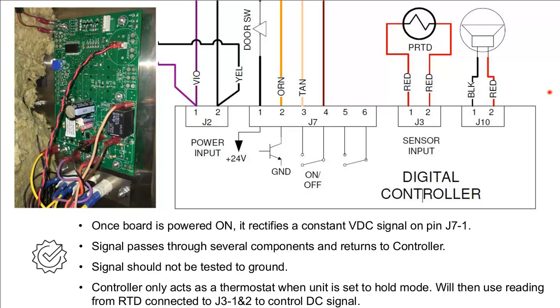I'll draw your attention to the fact that the controller does have an RTD. In cook mode, the controller outputs a constant DC signal. It does not modulate the signal based on the input of that RTD. The only time it will modulate that signal is when the unit is set in hold mode. But in cook mode, general use, it is a constant output.